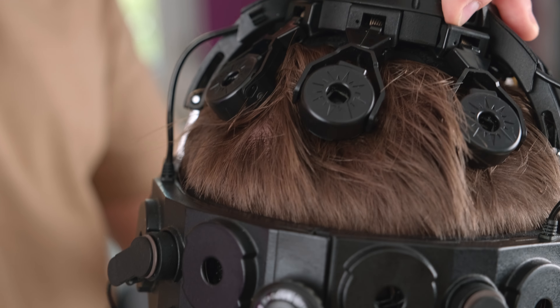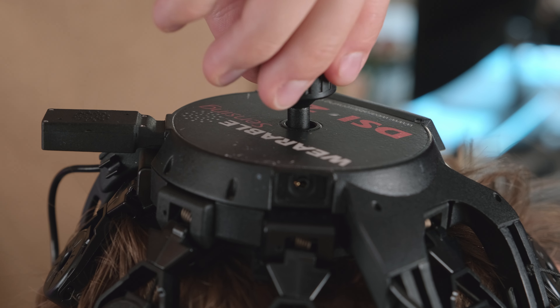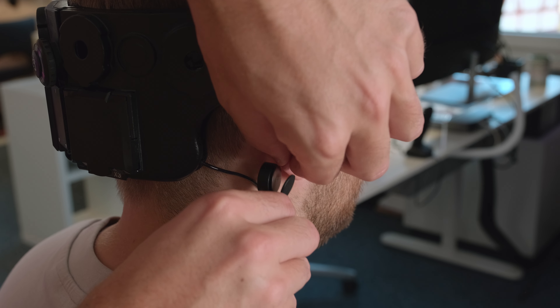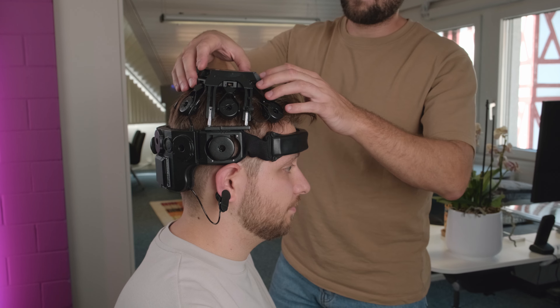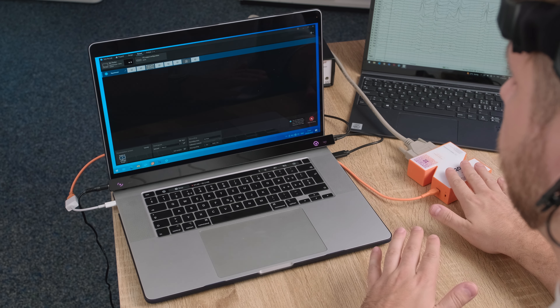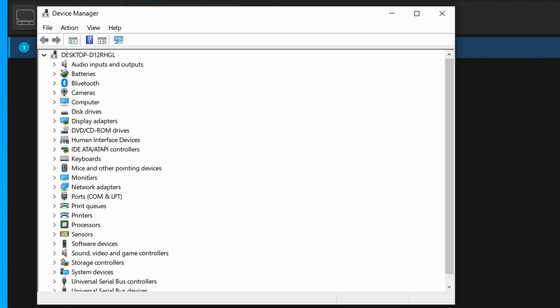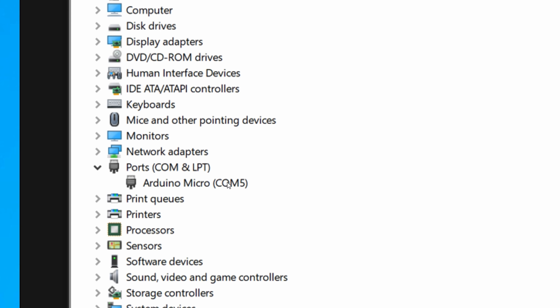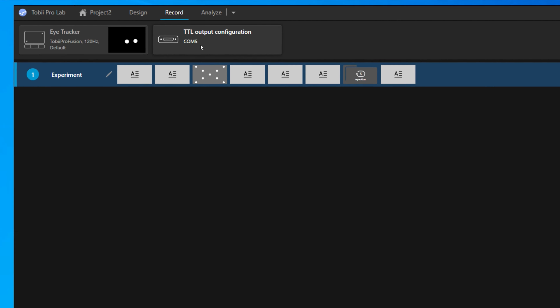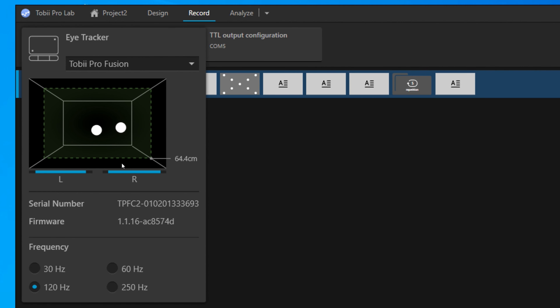So now let's get the DSi24 set up. With the EEG running and eye tracking going, everything is beautifully connected through the MMBTS. All that's left to do is right-click on the Windows Start button, select Device Manager as explained in our MMBTS series, go to Ports, COM and LPT, and find that the MMBTS has COM port 5. Select this as the TTL output configuration, select the Neurospec MMBTS as the device, and check that the eye tracker is properly connected.